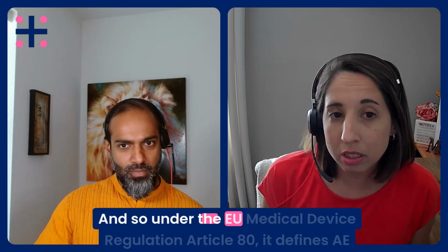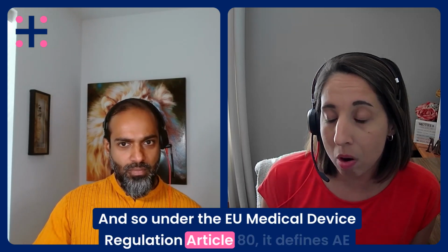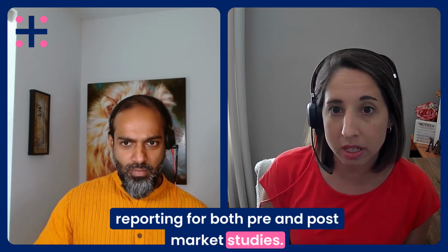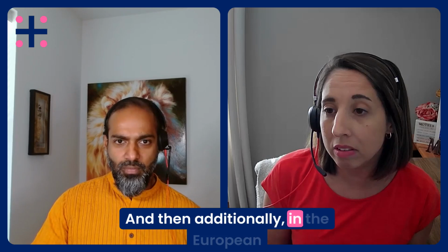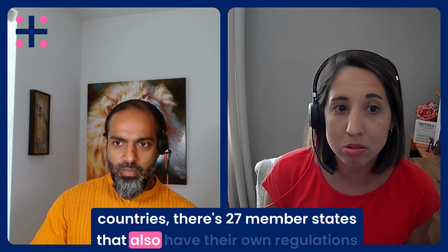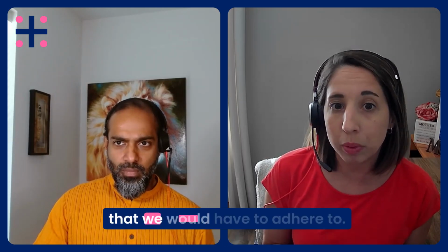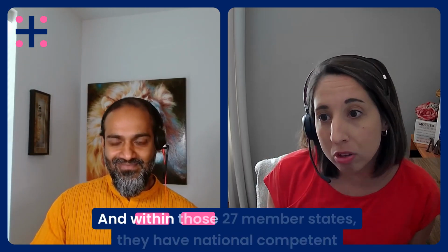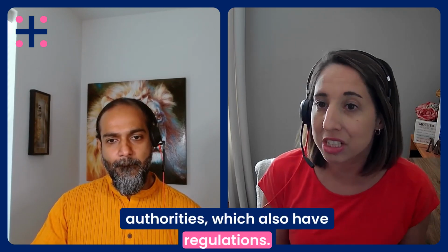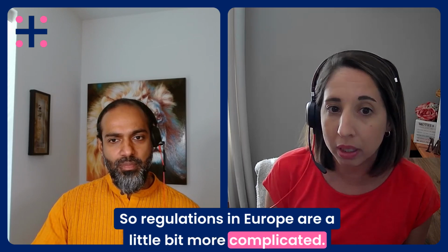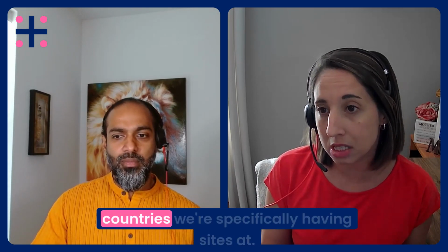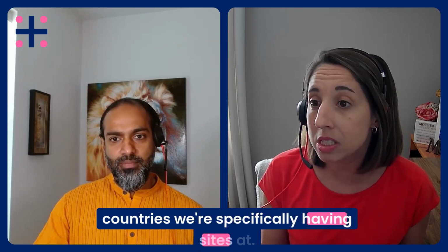And so under the EU Medical Device Regulation, Article 80, it defines AE reporting for both pre and post-market studies. And then additionally, in the European countries, there's 27 member states that also have their own regulations that we would have to adhere to. And within those 27 member states, they have national competent authorities, which also have regulations. So regulations in Europe are a little bit more complicated. We would look at the EU MDR regulations and then whatever countries we're specifically having sites at.